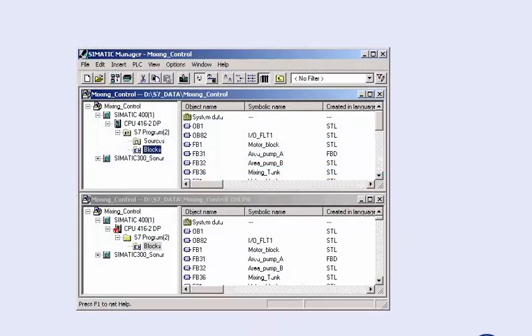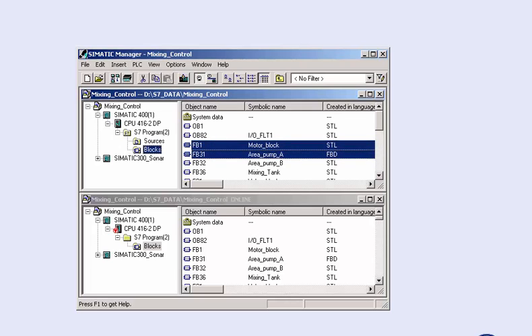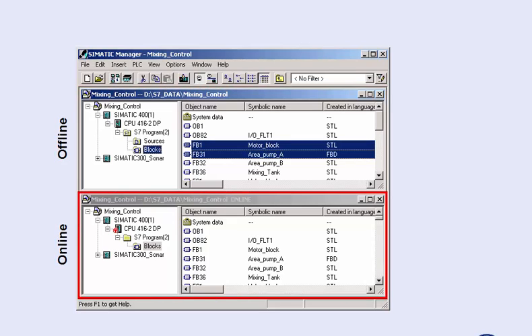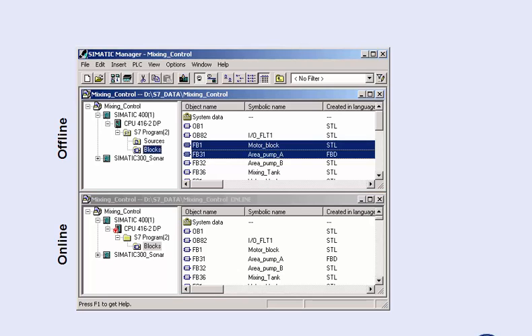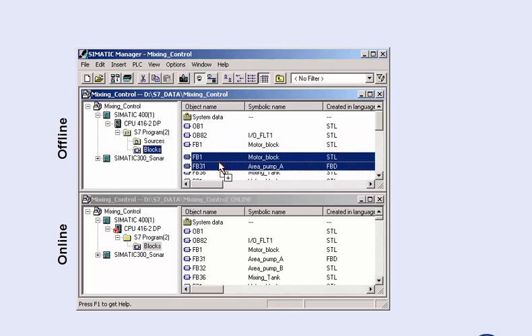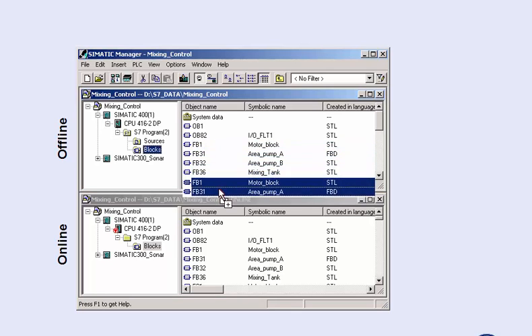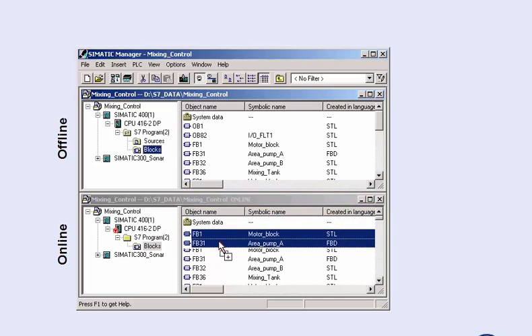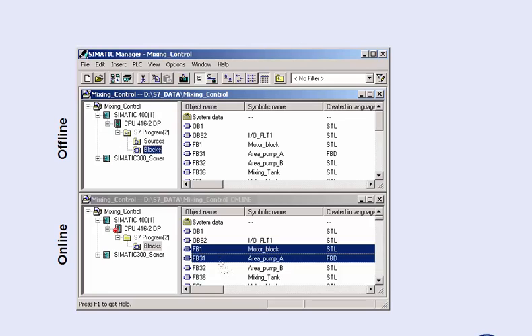If, for example, during later commissioning phases only a selection of blocks are to be loaded into the CPU, the SIMATIC manager gives you the opportunity of viewing the blocks on the programming device in the offline window and the blocks in the CPU memory in the online window. With drag and drop, you drag the desired blocks from the offline window to the online window of the CPU and perform the selective load procedure.